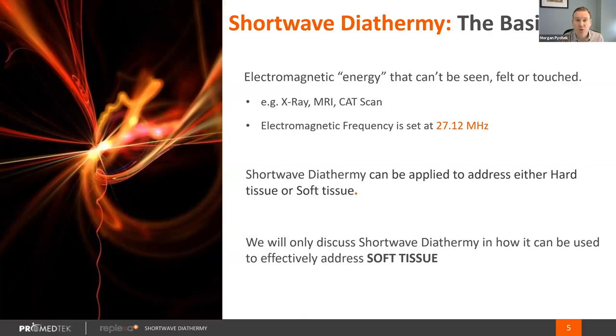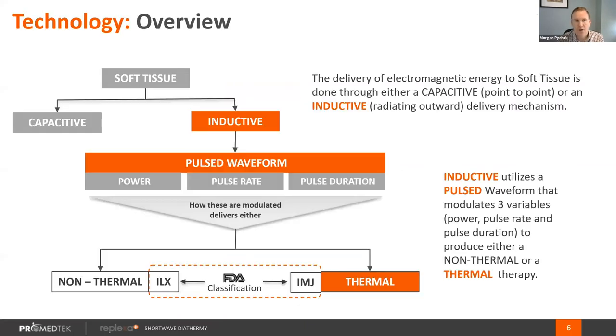We are typically tuned for soft tissue, and it can also be used in hard tissue. Shortwave diathermy as an electromagnetic falls under the same therapy tree as things like MRIs and CT scans or bone growth stimulators, where the therapy provides a treatment but can't be seen or felt. Within that shortwave diathermy tree, we really have two main things that we modulate: the delivery mechanism and the power settings of the therapy, which result in a classification from the FDA and then subsequent indications.